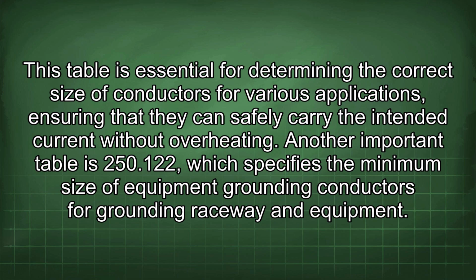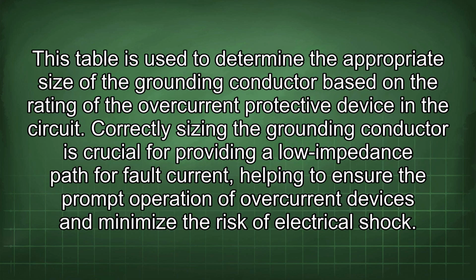Another important table is 250.122, which specifies the minimum size of equipment grounding conductors for grounding raceway and equipment. This table is used to determine the appropriate size of the grounding conductor based on the rating of the overcurrent protective device in the circuit. Correctly sizing the grounding conductor is crucial for providing a low impedance path for fault current, helping to ensure the prompt operation of overcurrent devices and minimize the risk of electrical shock.